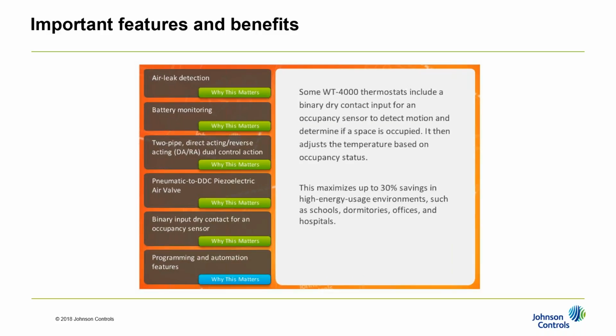The binary input for the dry contact is important because although this allows either your BAS or your programmable schedule to get some energy savings, if you're in something like a school where a classroom may be occupied only half the time, a motion sensor will get you up to an additional 30% energy savings. So the availability of this contact is not a minor nicety. I'd encourage, in those situations, including the occupancy sensor with your purchase.